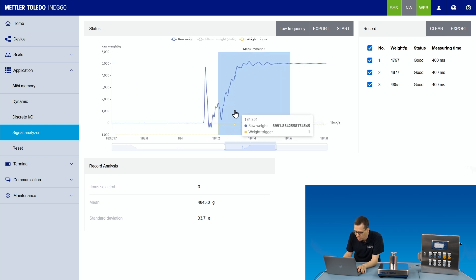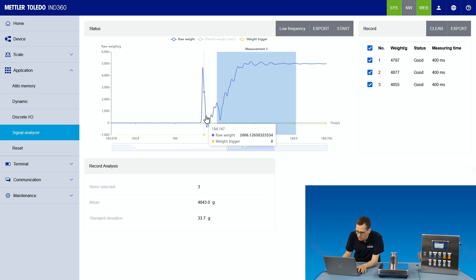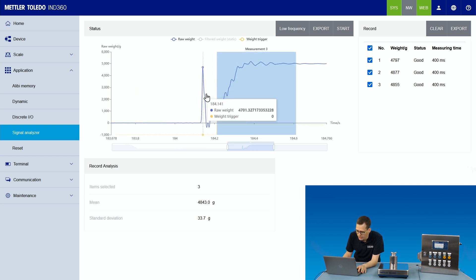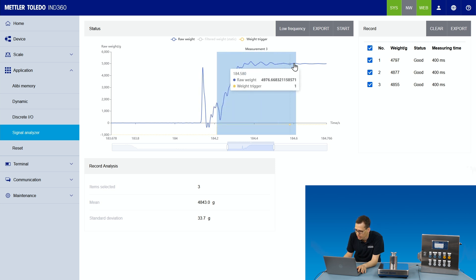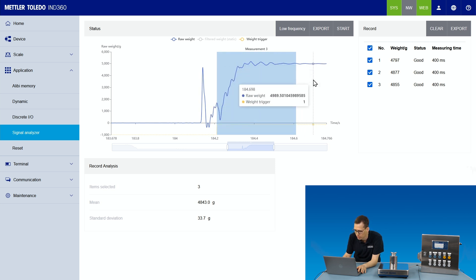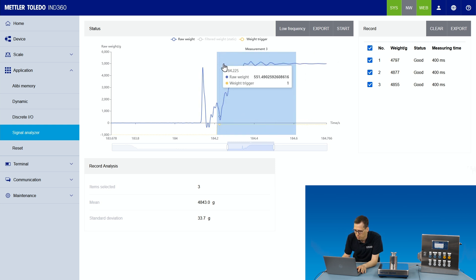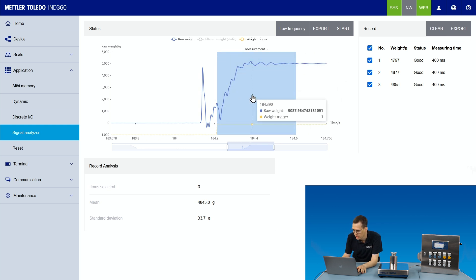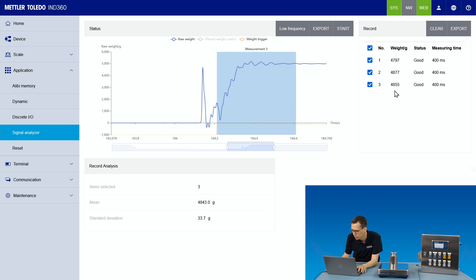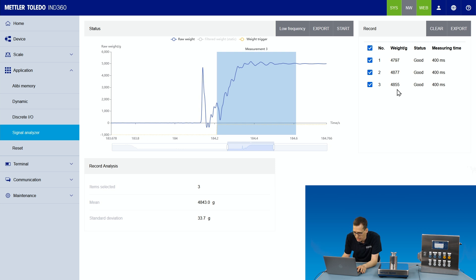And then stop the signal analyzer so we can look at the weight trace in more detail. So I'll zoom in here. Let's see here, okay, the object hits the scale and then we see the weight increasing up to 5 kilograms and then stabilizing somewhere here. This blue part here, measurement 3, this is the area where we take the measurements which resulted in 4.855 kilograms. Which is not the 5 kilograms we actually want to have. So why did this happen?